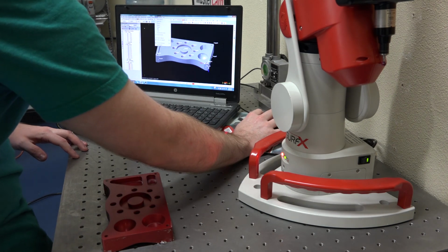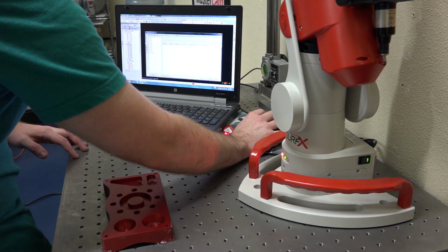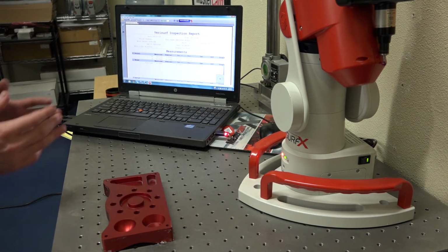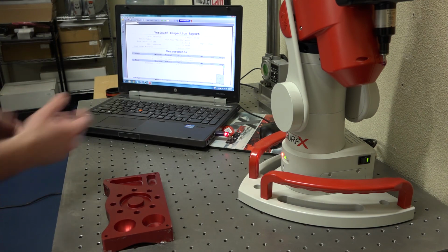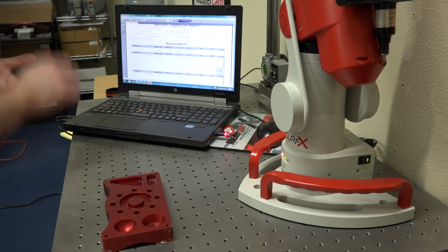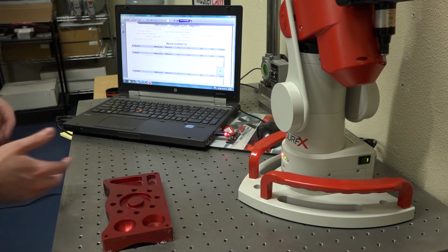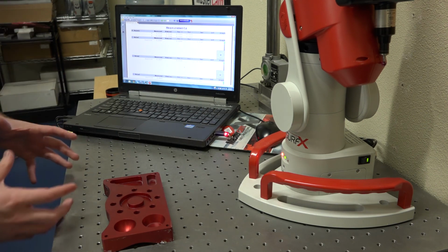And now what I can do with this information is I can generate a report. So I'll right click on my features and I can say report. I'll have it generate a report based off all this information, and it's going to go through and process it and output either a PDF, HTML file, Excel file, whatever you want, and will generate a report, give me nominal information about positional tolerance, diameter tolerance, roundness, depends on what you're doing. For a line, usually it's angle and length and straightness. Holes have a positional tolerance, roundness tolerance.